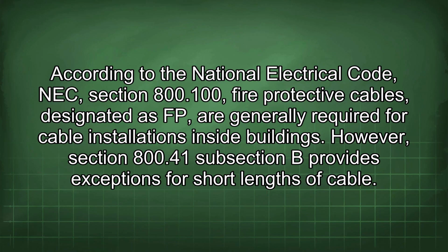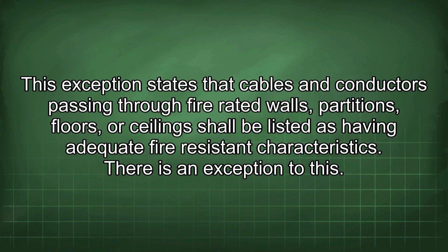According to the National Electrical Code, NEC, Section 800.100, fire protective cables, designated as FP, are generally required for cable installations inside buildings. However, Section 800.41 subsection B provides exceptions for short lengths of cable. This exception states that cables and conductors passing through fire-rated walls, partitions, floors, or ceilings shall be listed as having adequate fire-resistant characteristics. There is an exception to this.